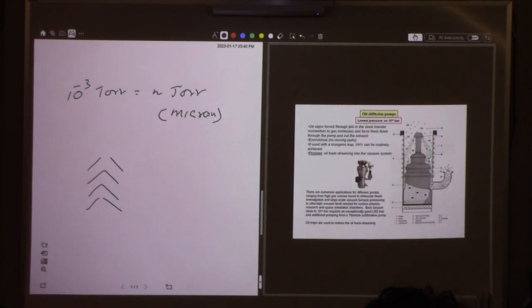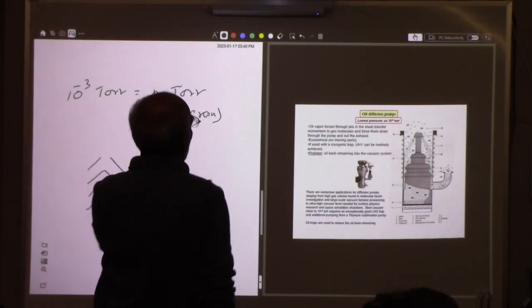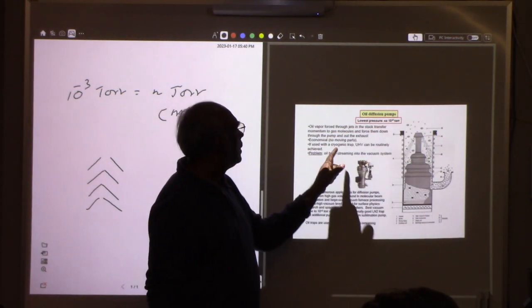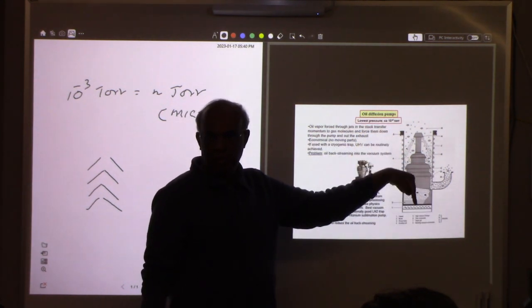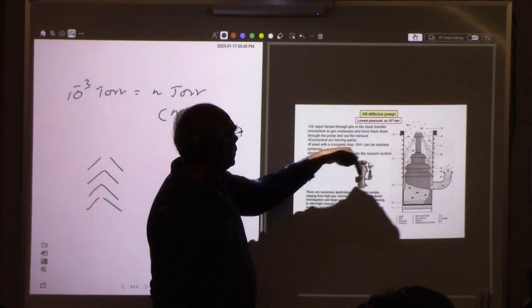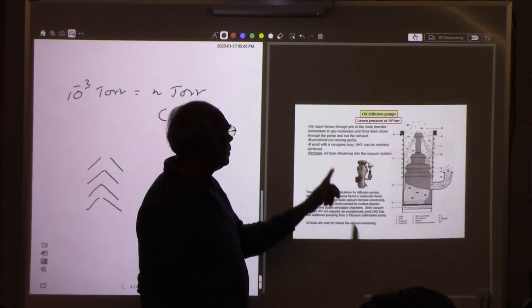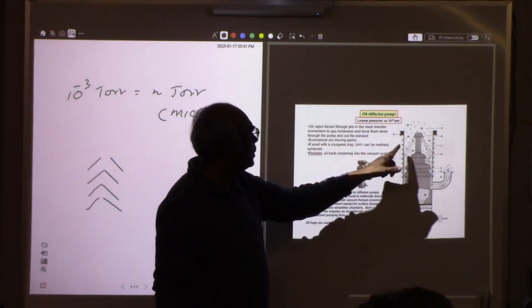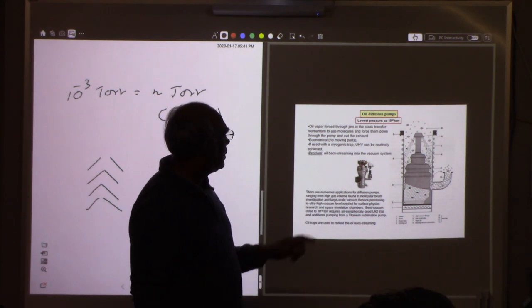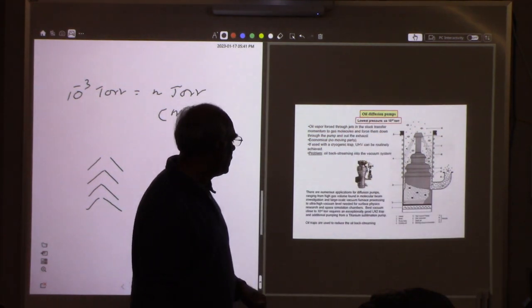Is there a reason why you use oil and not just another hot liquid like water? No, you need to have very high momentum particles, right? It's very hard to get that kind of momentum without some highly viscous material. So you can see how that works here. See, oil vapor goes through jets, right? The stack transfers momentum, that's the whole idea, to the gas molecules, and forces them down this way. So then you have to use the cryogenic trap. Otherwise, that's the problem: oil backstreaming. That's why you have to put this one.